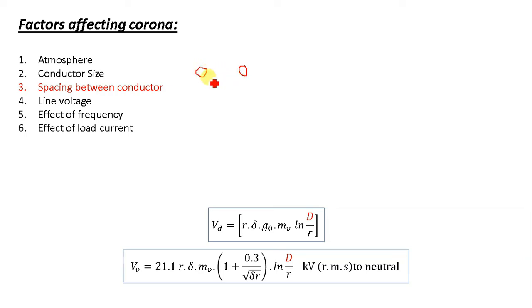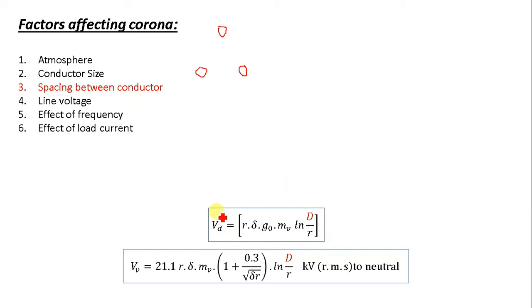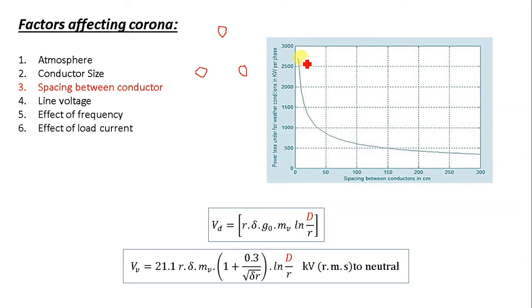However, increasing the spacing increases installation cost because the arms of the tower become wider. The spacing varies the value of d — in equilateral triangular configuration all distances are equal to d, otherwise d is the mutual GMD. This affects Vd and Vv, and ultimately the corona. As spacing between conductors increases, power loss in corona decreases.